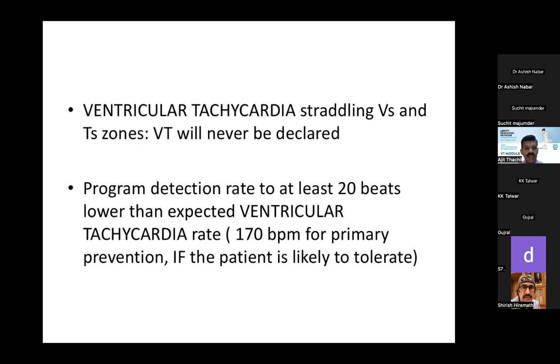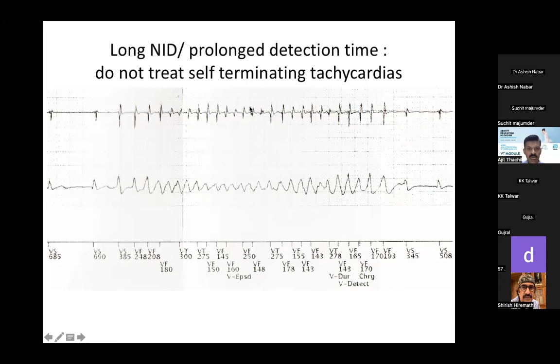A longer NID helps to not treat self-terminating tachycardias. Here is a self-terminating rapid ventricular arrhythmia. Because the NID was longer than this, it did not give an inappropriate shock for this. If the NID, or the number of intervals detected, was shorter, it would have given an inappropriate shock for this tachycardia, which would have terminated. So how long can you put the NID, the number of intervals detected?